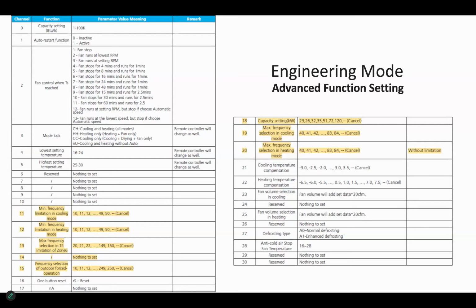All right, so here's where we were talking about enhanced defrosting, or the defrost. We had a question on that, correct? Yep. Okay. So we have an operation, a mode for enhanced defrosting. It can be set either through engineering mode on this remote or on the AHU, or there's a dip switch in the outdoor unit, SW1-4. SW1-4 in the outdoor is the normal or enhanced defrost switch.